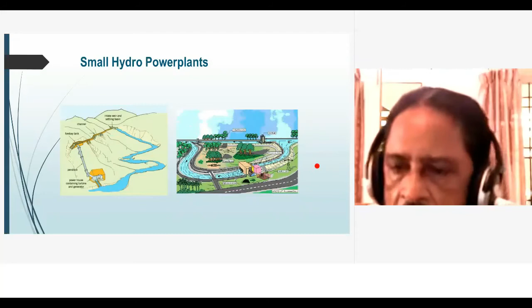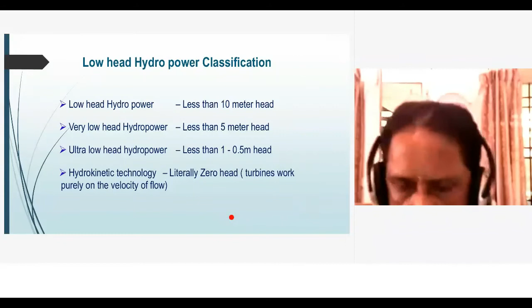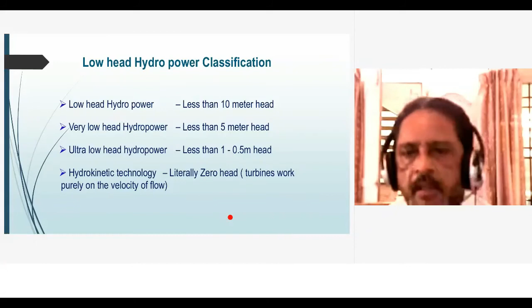This is a low head classification. Low head is less than 10 meters, very low head is less than 5 meters of head, and ultra low head is less than 1 to 1.5 meter head. You also have zero head turbines, called hydrokinetic turbines or vortex turbines.